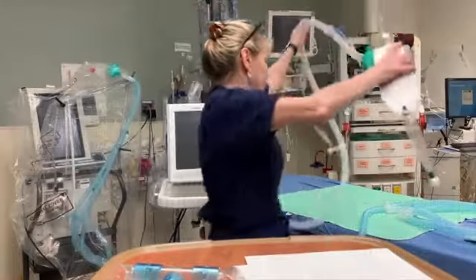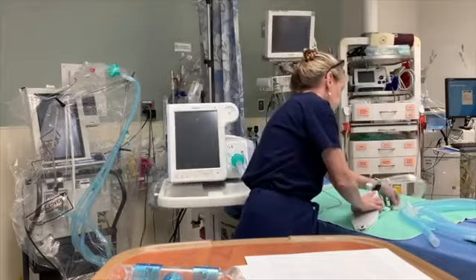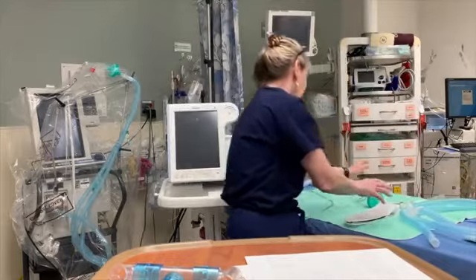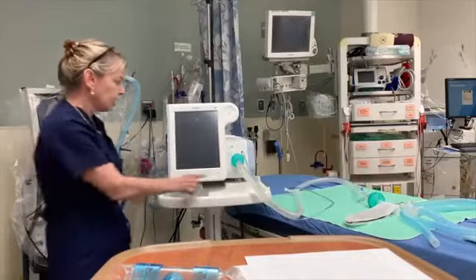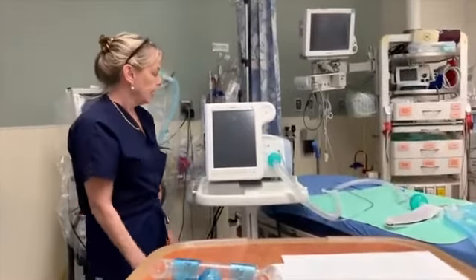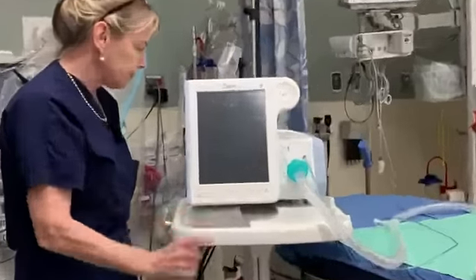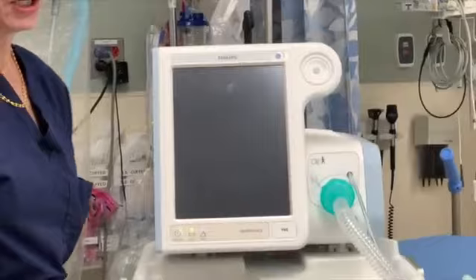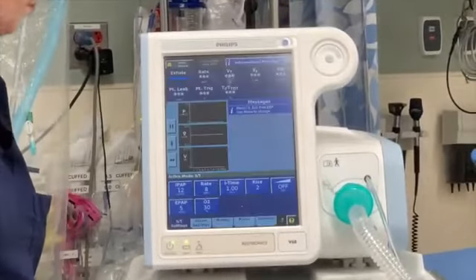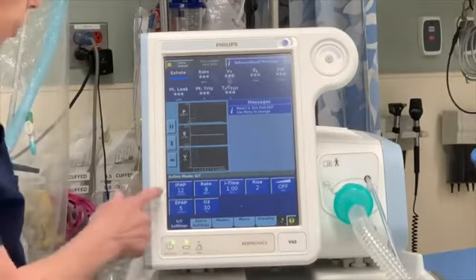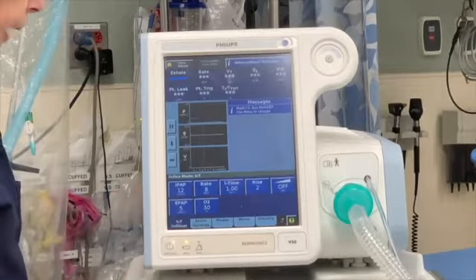So this is the whole setup of the tubing. I'm going to leave the test lung right there so you can see it working. Now the machine. Again, you're lucky if it's a V60. That means it can be used in ventilation. I'm going to turn it on. And the first thing you're going to see, it's going to be in the mode for Bi-pap, which is what we usually use it for. It's 12/5. That's a typical Bi-pap setting.